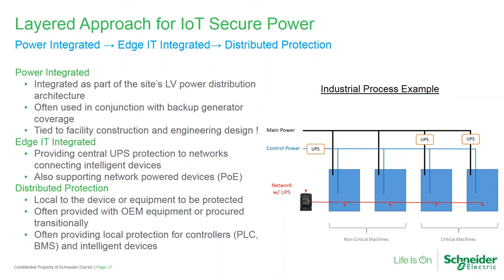In process control environments, we're more likely to see central control power UPS. In the example shown, there are two separate power feeds coming to the machine: one for main power and one for control power. A typical main power UPS, depending on system size, might be a three-phase UPS fed from 480 volts, feeding 480 volts to a system that goes into the main circuit breaker or fuse set for the machine. It's actually the power source for the machine.